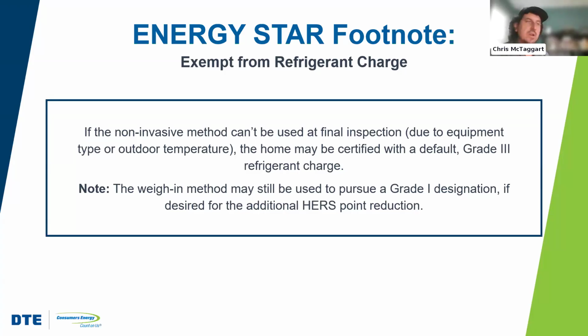get additional points. So the other value of the HVAC grading process, regardless of whether or not the installing contractor has to be credentialed or not, the other big value is that builders can get additional points through pursuing HVAC grading. I will say particularly for cold climate heat pumps, this can be very significant. Homes can achieve 5 or more HERS index points through getting a grade 1 installation. So it is worth it to builders to work with a rater that is qualified to perform HVAC grading, just insofar as it can really help the process and to get the builder some extra credit.